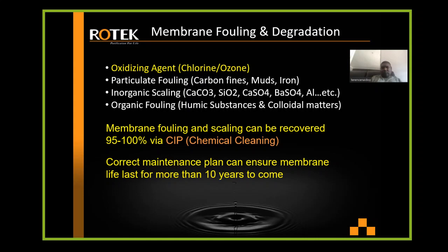Inorganic scaling includes calcium carbonate, silica, calcium sulfate, barium sulfate, aluminum, etc. Those are inorganic scaling, and they usually happen after 3 months. So if you have a fouling problem within 1 month, particulate and organic are the things you should focus on solving with the pre-treatment. Okay.